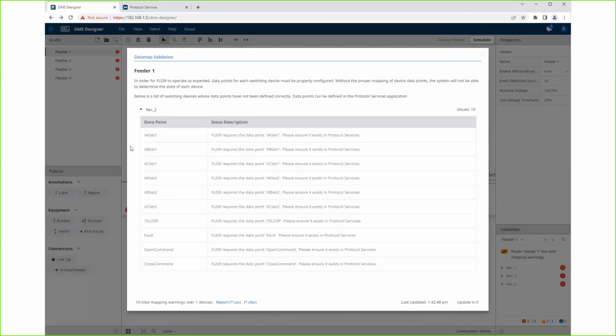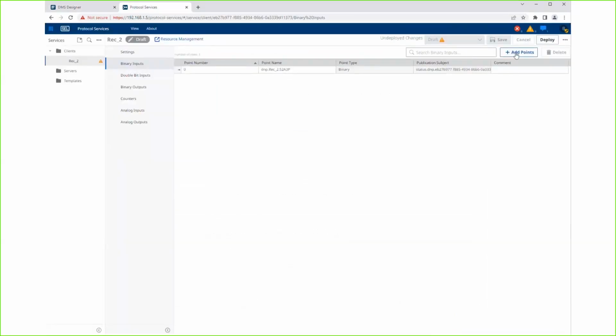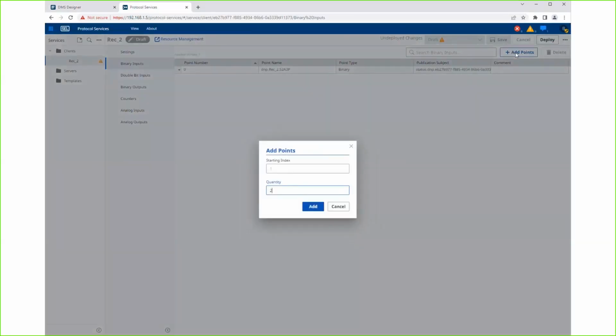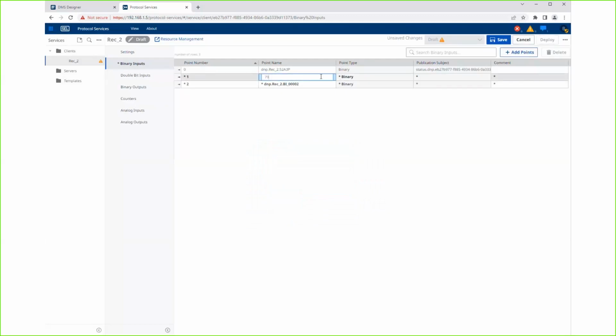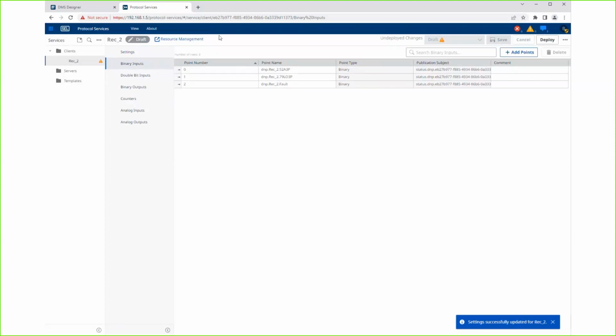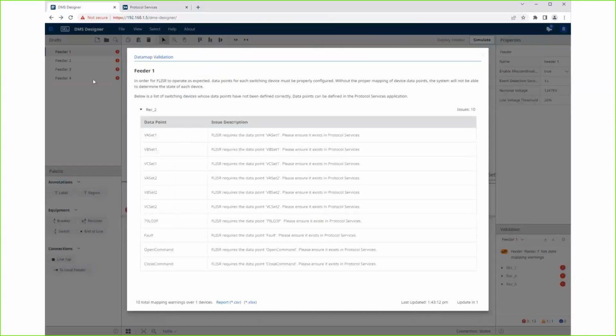And you can see that IA, B, and C is gone and 52A3P is gone. DMS Designer every 5 seconds checks for data. And if it finds it, it will hook itself up. So there is no wiring of data to be done here. Everything is done by name. If you name it what DMS Designer expects, FLISR can use it, and it will use it automatically. So you can see things disappearing from this table as it checks for information.